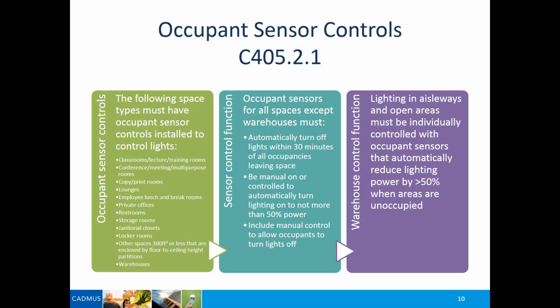And this requirement would actually require an occupancy sensor in addition to the daylighting controls, so that if there's enough natural light in that space, the occupancy sensor in this case would only turn it on to 50% power, or the occupancy sensor would kick the lights on, but the daylighting control would dim the lights down to what you need from a foot-candle standpoint, to make sure you have adequate light in that space. So the two controls would be working hand in hand to provide the right level of lighting for that particular space.